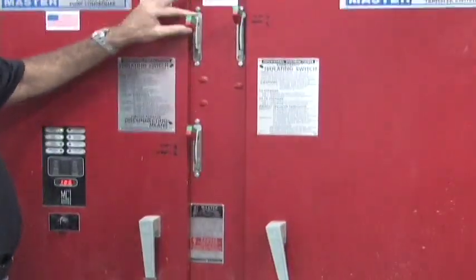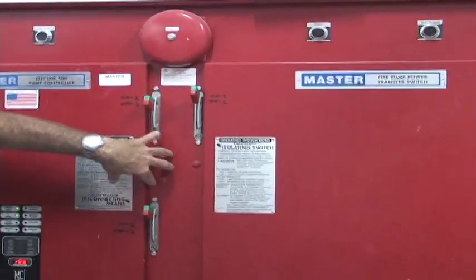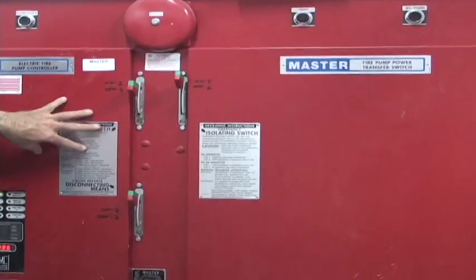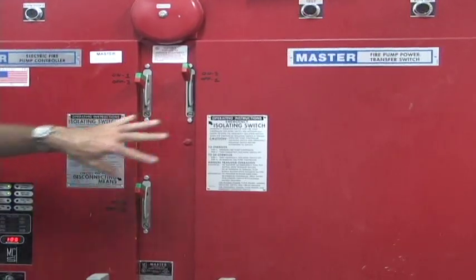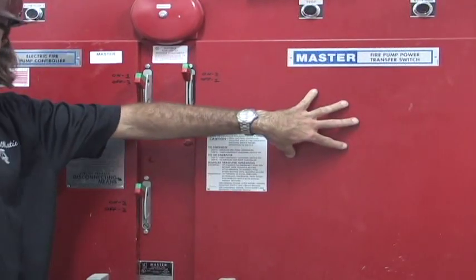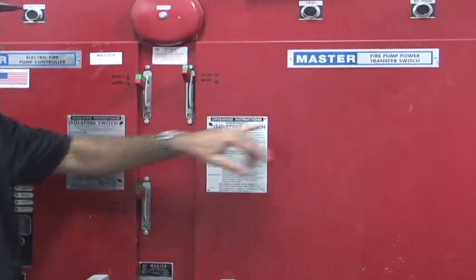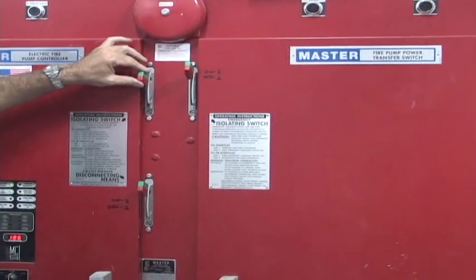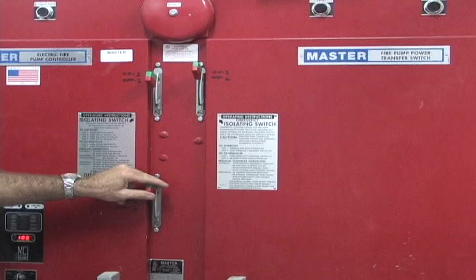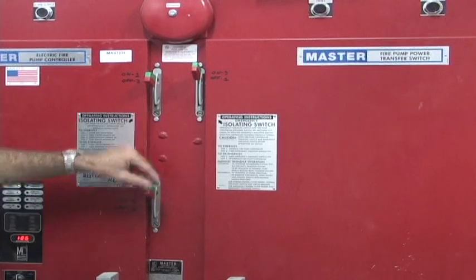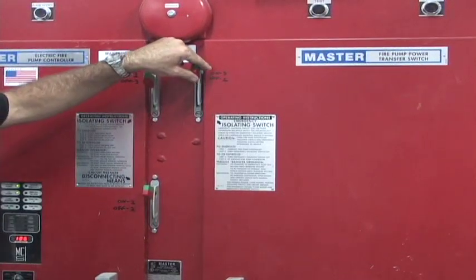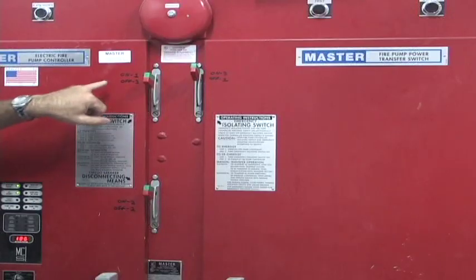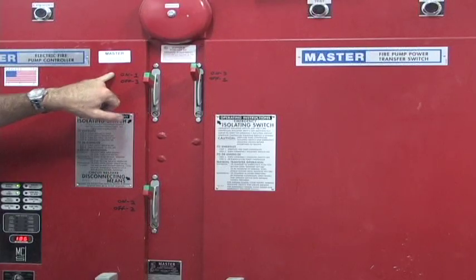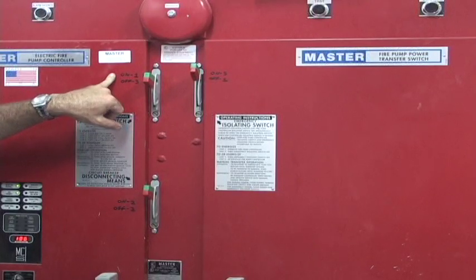We have 3 switches that work our fire pump. The left side of this controller is going to be our normal power, or our FPL. The right side is going to be our emergency or our transfer switch side. We've got 3 switches: our isolating switch, our circuit breaker disconnecting means, and our emergency isolating switch. I have in the 3 corners the procedure of turning the fire pump on and turning the fire pump off.